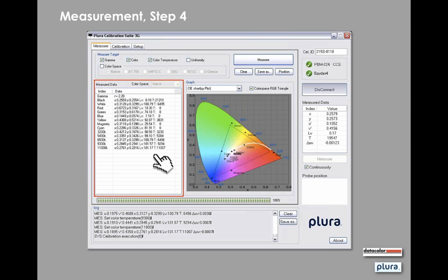If I may interrupt as well, to answer Gustavo Carrillo, I hope I'm pronouncing it correctly. Forgive me if I don't. If you use the calibration parameter and it was incorrectly entered, two scenarios could happen. Either the calibration will fail and it would not continue, and all you have to do is go back and reset the monitor. Or if it does go through and your parameters went through incorrectly into the monitor, you can reset the monitor to factory default, and there is a process for that. So you don't have to worry if for some reason you had an issue with the calibration.